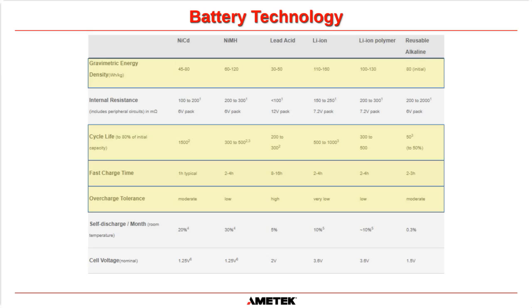So we can see we've got NiCads on the left. We'll forget this one here because basically that's talking about your household batteries, your 9-volt batteries, your AA batteries and stuff like that. But one of the most important things is the gravimetric energy density. In other words, it's the watts that you can get out of the battery per kilogram. So the higher that value is, the more power per size, I suppose, you can get out of it. You can see here that for NiCads, it's 45 to 80. For lead acid systems, it's less. They're not as energy dense. And for lithium ion, they're extremely energy dense. We're talking about nearly 3 times the energy density of the other 2 main technologies there. So that's one of the main differences, how much power a battery can deliver compared to its relative size.